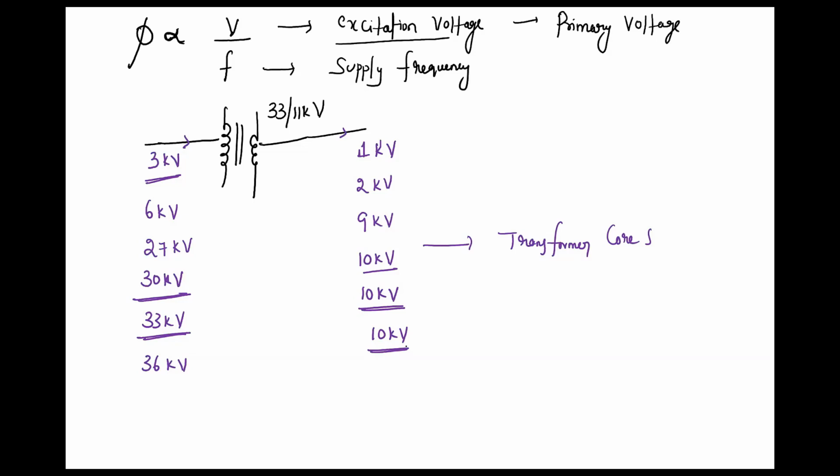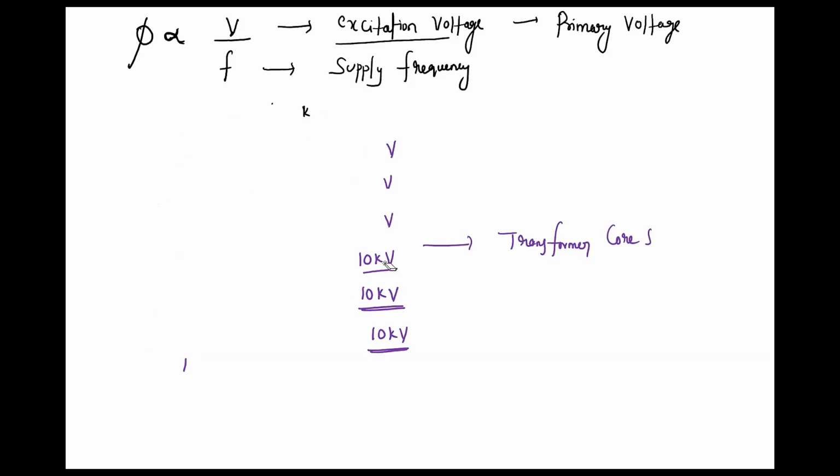Why? Because for the complete CT operation, PT operation, and transformer operation, we assume they have a constant voltage transformation ratio, and we have devised complete protection schemes on that basis. All protection schemes operate on what? CTs and PTs. We are assuming that the CTs and PTs are properly stepping down the voltage and currents, and we are designing the protection. So if the CT, PT and normal transformer core saturates, then the complete switchgear and protection will become a blunder. So the overflux relay is very important.